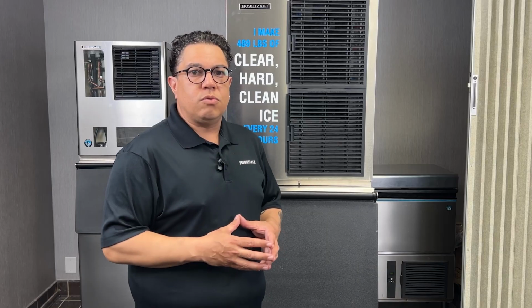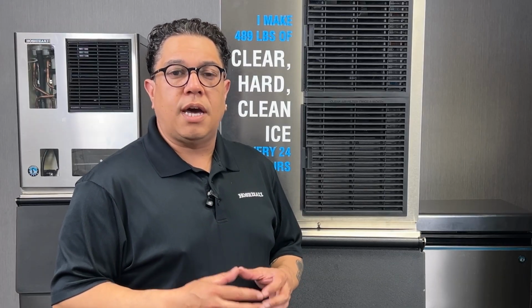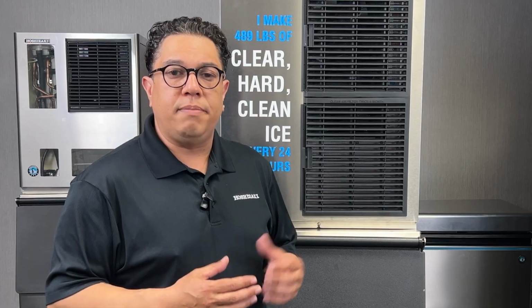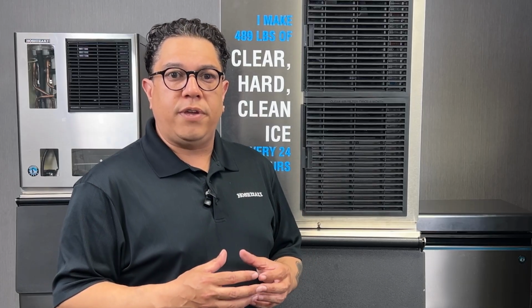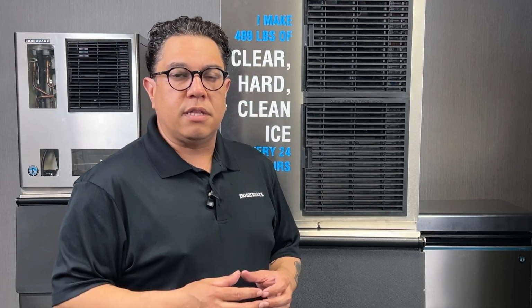Hot water migration is one of the things most difficult to diagnose on that machine, because you'd have to be there for the next 7 days until it faults out, temping the water. To be able to confirm that we have hot water coming into the machine, on the back side of the unit where the water line meets the machine, there's always a brass fitting. We're going to put a little dab of Vaseline on the top.